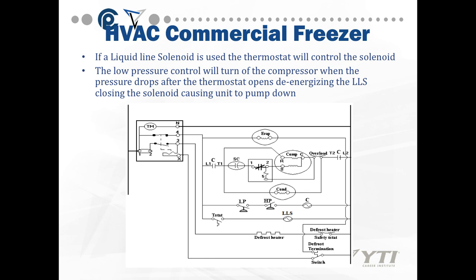If a liquid-line solenoid is used, the thermostat will control the solenoid, and the low-pressure control will turn off the compressor when the pressure drops after the thermostat opens. It de-energizes the LLS, closing the solenoid, causing the unit to pump down. A pump-down system removes all the refrigerant from the evaporator and puts it into a holding area in the condenser on the system, preventing liquid slugging back to the compressor, using the condenser and the receiver.